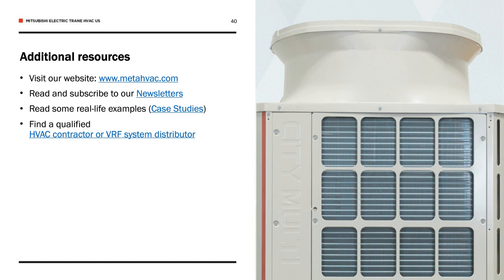When it comes to the terminal devices, CO2 sensors, humidity sensors, central controllers that would live on a VRF system, you need something to pull them all together, and avoiding pulling multiple networks becomes possible because you're now on that main trunk, in that common protocol like BACnet. What's happening in our industry is that not only are the larger package systems, rooftop units, chillers, and VRF systems becoming BACnet enabled, but smaller devices, CO2 sensors, wall controllers, wireless wall controllers, and application controllers that used to need a network are now becoming wireless. They're becoming enabled to take part in an open protocol like BACnet. So you're quickly getting to the point where you don't need multiple networks within a building. You're able to survive on that one platform.